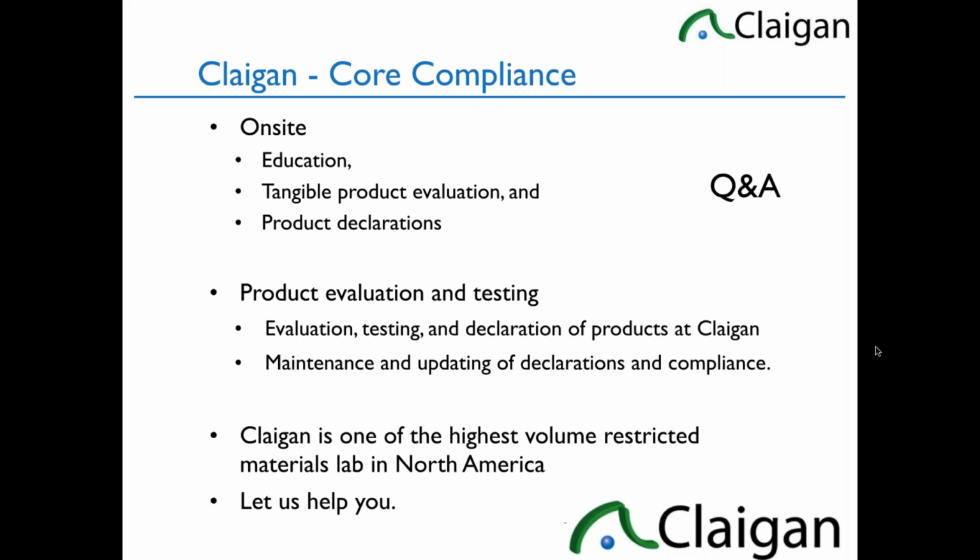How would your testing strategy practically work for huge electronic medical devices that consist of hundreds of thousands of components? You recommend testing at all for such complex devices? It depends. It depends a little bit on the regulations. So RoHS, you have to be a little more stringent, so you have to be more comprehensive there. But we test large medical devices all the time. Normally, we test them at your site. So the on-site version we do is very effective.